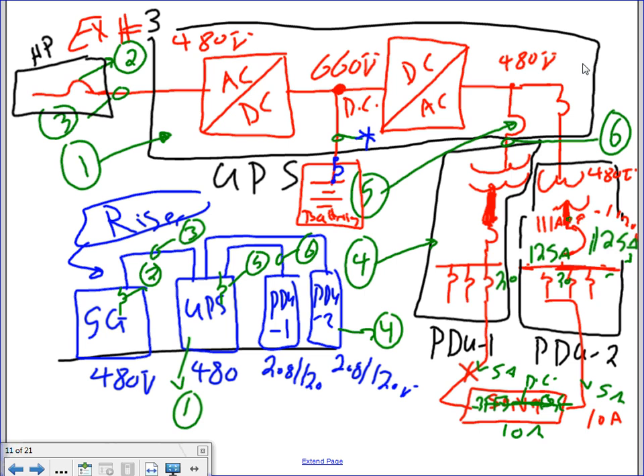And then the power is distributed through what are called power distribution units, PDUs. Cool? So here's a big box, taking the AC, converting it to DC, tying it to the batteries, and inverting it back to AC. Then two or three circuit breakers send it to the PDUs. Also, the UPS could be in one room, guys, and the PDUs typically in a completely different room. Two PDUs, and these PDUs are panels sitting against the wall and feeding all these racks of computers.